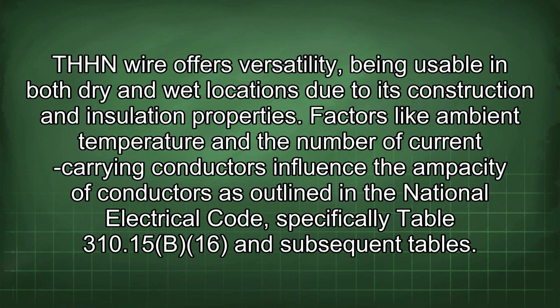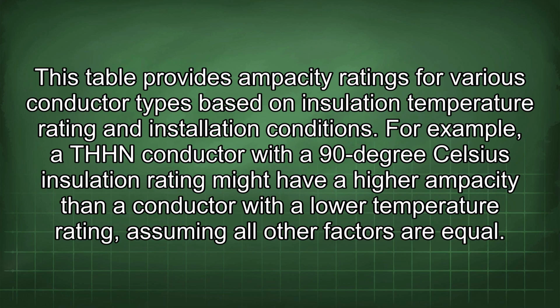Factors like ambient temperature and the number of current-carrying conductors influence the ampacity of conductors as outlined in the National Electrical Code, specifically Table 310.15(B)(16) and subsequent tables. This table provides ampacity ratings for various conductor types based on insulation temperature rating and installation conditions. For example, a THHN conductor with a 90 degrees Celsius insulation rating might have a higher ampacity than a conductor with a lower temperature rating, assuming all other factors are equal.